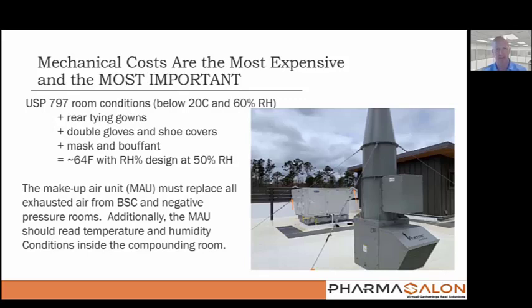Although it's not explicitly stated, the intention is that no air introduced into the hazardous drug room would ever be recirculated back into an HVAC system to be reintroduced either into the compounding room again or other spaces that it shares its HVAC trunk lines with. So the intent of the chapter, when we quote-unquote externally vent, is that we need this type of equipment. I can tell you, look at this right here, this is called a jet plume. It's sending perfectly good air out of the building. Once it goes out in the atmosphere, we don't get that back. And you have to replace it.